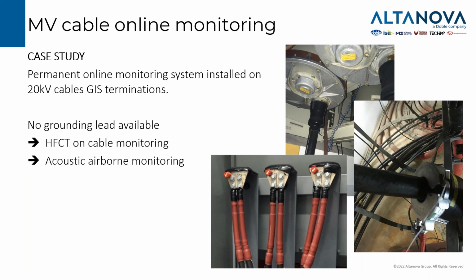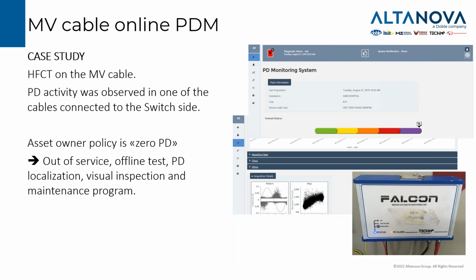We can now take a look at a case study related to a similar case. So, PD monitoring on a medium voltage cable termination. We do not have any ground available, so we have to put the HFCT directly around the cable, and we have acoustic airborne monitoring at the termination. Our standalone unit for medium voltage testing detected a PD activity on one of the cables, and this information was then managed by the user.